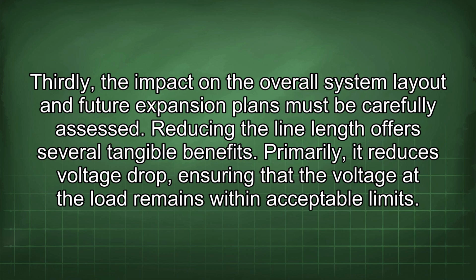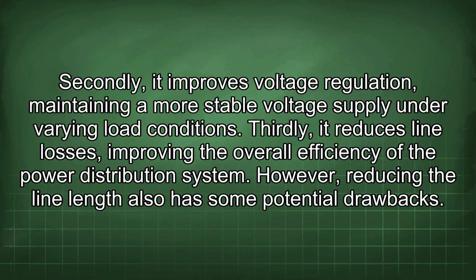Reducing the line length offers several tangible benefits. Primarily, it reduces voltage drop, ensuring that the voltage at the load remains within acceptable limits. Secondly, it improves voltage regulation, maintaining a more stable voltage supply under varying load conditions. Thirdly, it reduces line losses, improving the overall efficiency of the power distribution system.